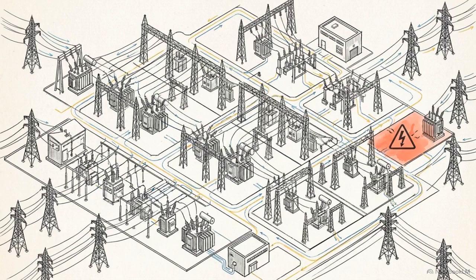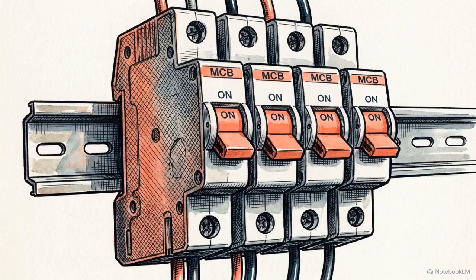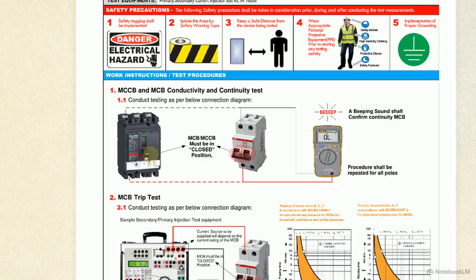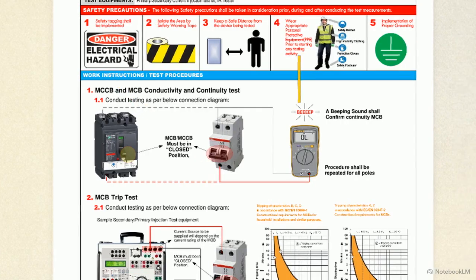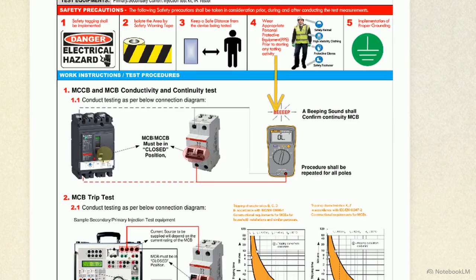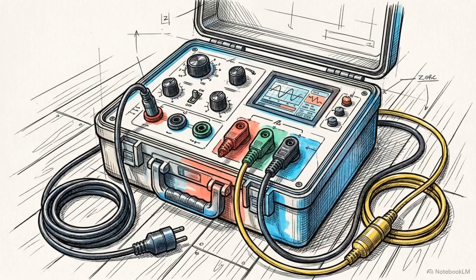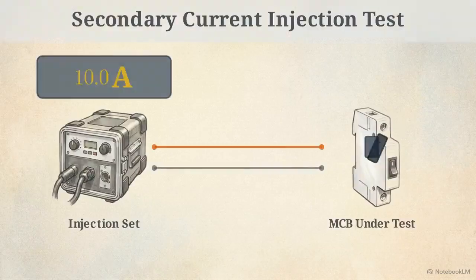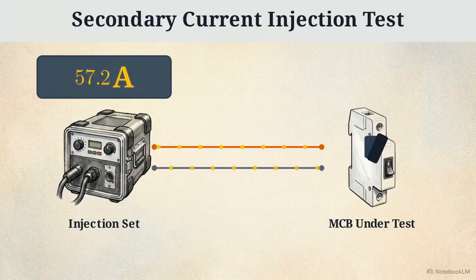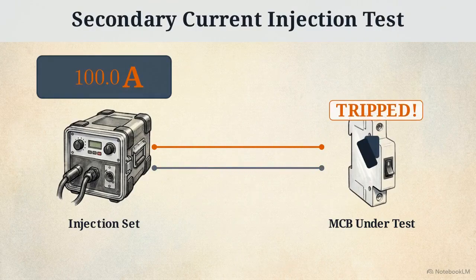The next layer of testing verifies the dynamic fault protection. Miniature circuit breakers, or MCBs, isolate localized overcurrent events before they spread to the main busbar. This procedure begins with a mechanical continuity check. With the breaker locked in the closed position, a multimeter is connected across the poles to prove an uninterrupted electrical path exists through the device. Once continuity is confirmed, the tester configures a secondary current injection kit. This machine simulates a fault by pushing precise levels of current through the MCB, scaled to its specific amp rating.